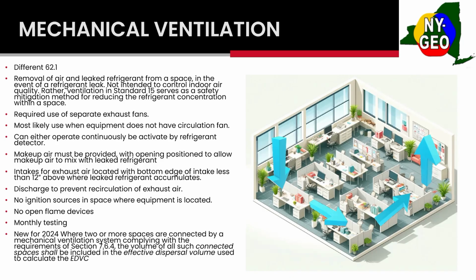So this mitigation system needs to be tested monthly. So another thing to add to any preventive maintenance schedule that you're doing. And lastly, for 2024, ASHRAE 15 released the new standard: 2 or more spaces connected by a mechanical ventilation system complying with the requirements, the volume of all such connected spaces should be included in your effective dispersal volume charge. So again, that's just saying if your space is connected by ductwork, you need to account for all those spaces that are connected.